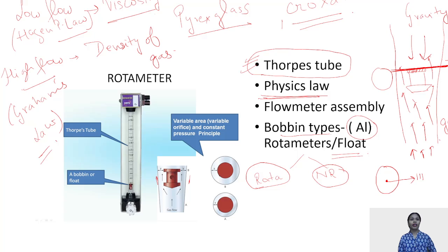Now, if your flow is dependent upon the viscosity and the density, then one thing is but natural, that all flow meters are calibrated according to the gas they are going to carry. You cannot interchange the pipeline connections of the flow meters. For example, suppose your anesthesia machine is undergoing some service, and the engineer connects the wrong pipeline with the wrong flow meter.